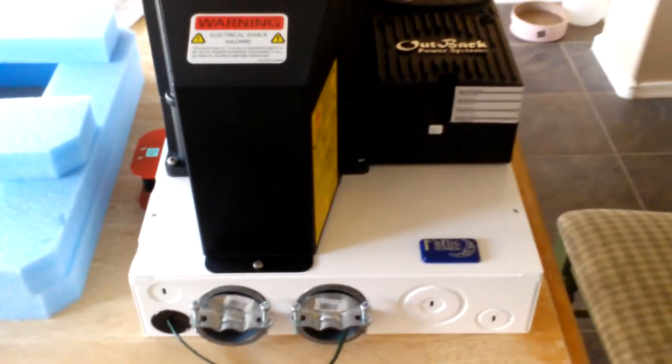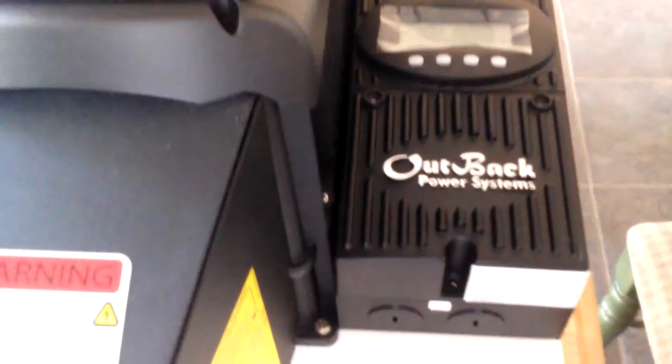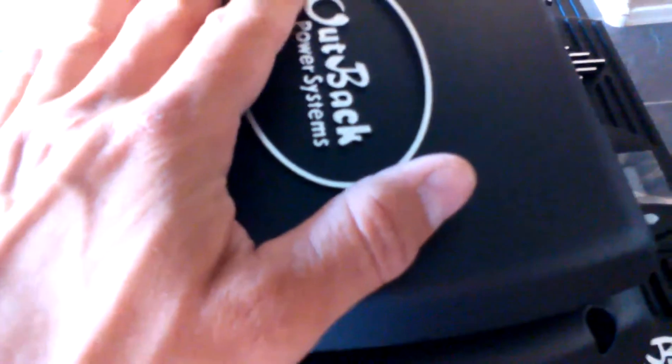I'll show you the electrical panel, or what they call the e-panel. I got it from Midnight Solar. It's got the Outback 48 volt inverter and the Flexmax 80 charge controller. Everything fits in this box — here are the breakers for the charge controller and here's the main breaker over there, a 175 amp breaker for the inverter, and breakers for a generator if needed.